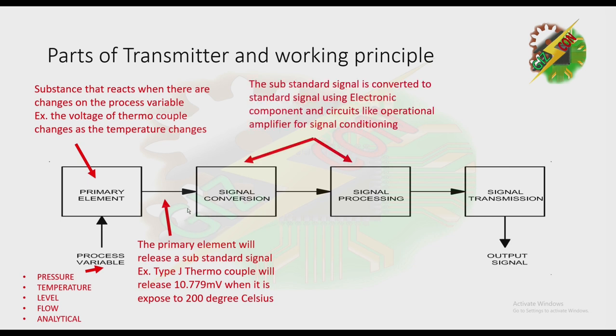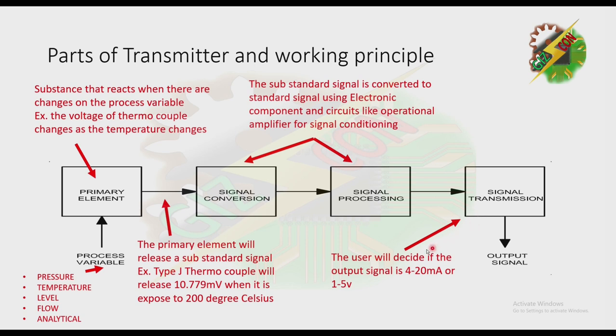The primary element releases a substandard signal. For example, a Type J thermocouple will release 10.779 millivolts when exposed to 200 degrees Celsius. Then we have signal conversion and data processing — at this stage, the substandard signal is converted to a standard signal using electronic components and circuits like operational amplifiers for signal conditioning. The 10.779 millivolts is now converted to a standard signal. For signal transmission, the user needs to decide if the output signal is 4 to 20 milliampere or 1 to 5 volts.